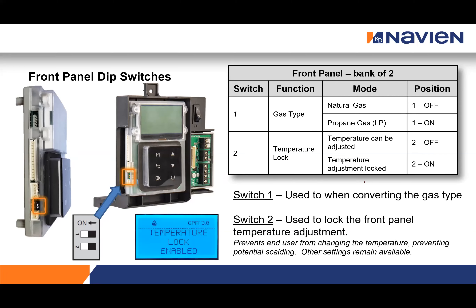Another important feature is the temperature lock dip switch. Right out of the box, all NPEs can be set anywhere from 97 to 185 degrees Fahrenheit, designed for both commercial and residential applications. After completing programming, I suggest flipping dip switch two to locked — this prevents anyone from adjusting the temperature simply by tapping the plus or minus button.